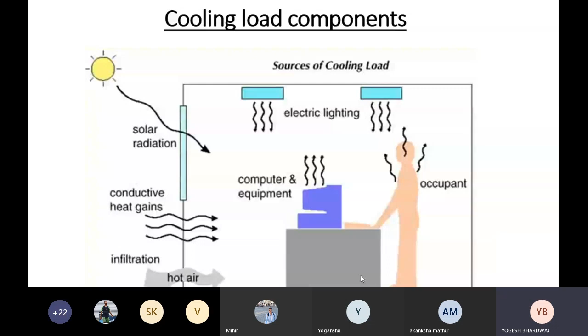Like cooling load components, as I told you, I can break them up into external and internal. Externals are heat gain through wall, roof, solar heat gain through window, conductive heat gain through window, and heat gain through partition wall or interior wall. Interior wall means I have two rooms side by side. If one room is air conditioned and the other room is non-air conditioned, in the air conditioned room I will maintain a temperature of 25, but in the unconditioned room the temperature may be 35, maybe 40.